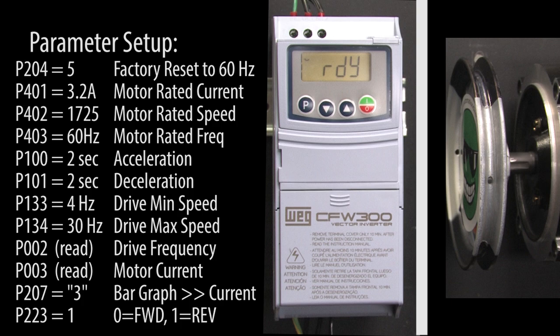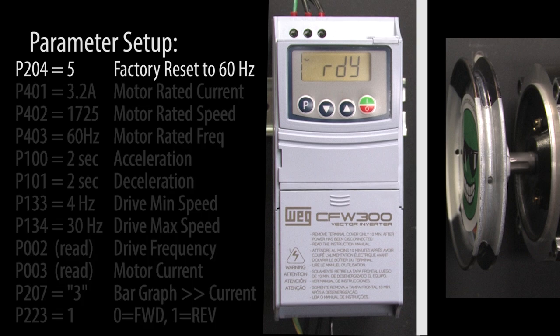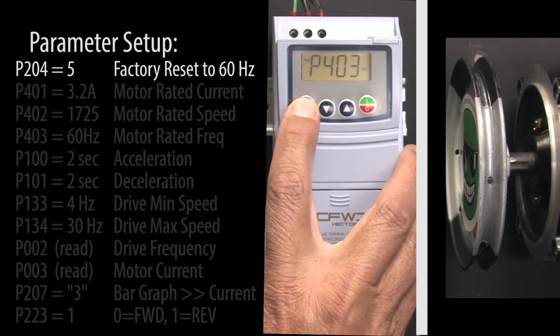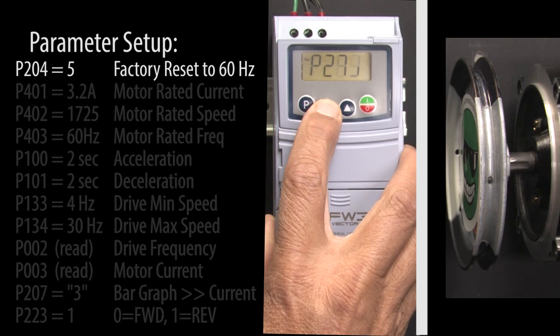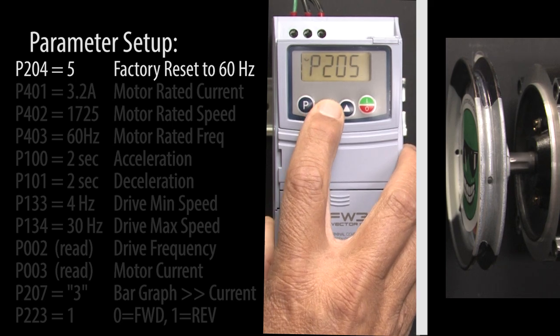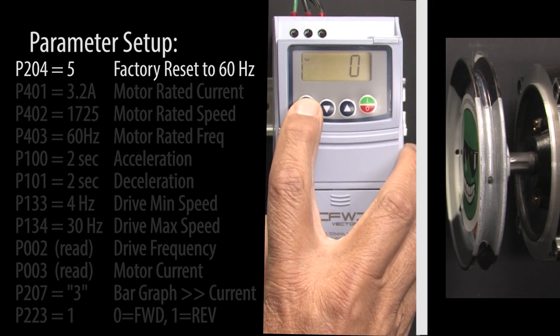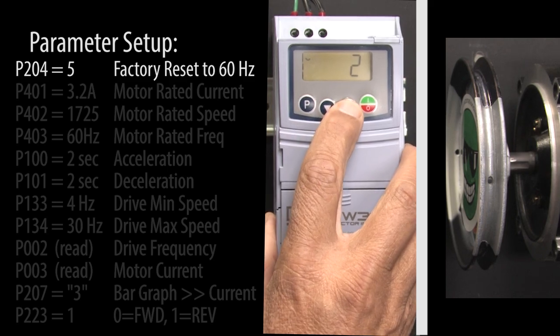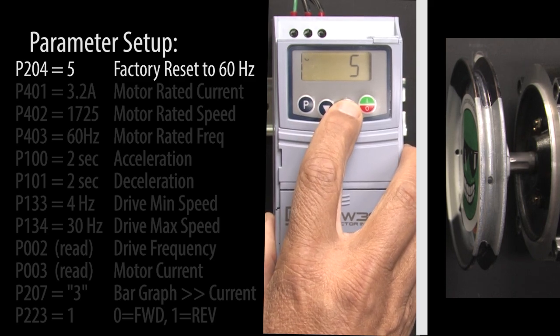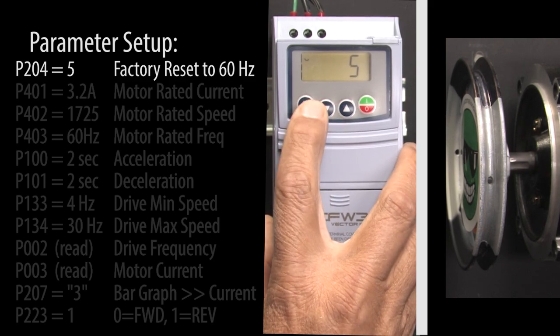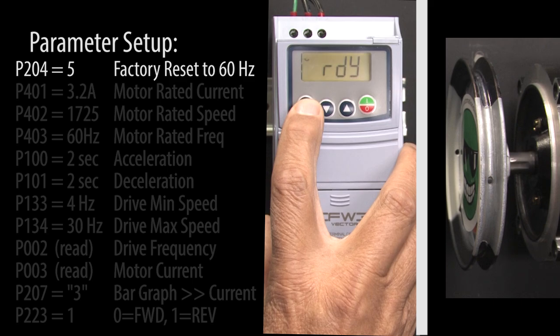Before doing anything, let's reset the drive to factory default so if you're following along we're both starting at the exact same place. Press the P button to get to the parameters and scroll to parameter 204. Hit P again so we can change the parameter to a 5, which resets the drive's parameters to factory default for 60 Hz, and press P to accept that.